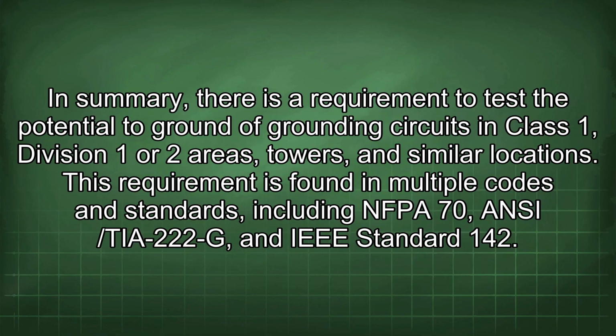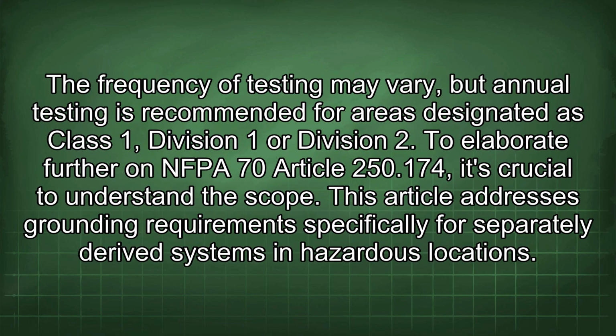In summary, there is a requirement to test the potential to ground of grounding circuits in Class 1, Division 1 or 2 areas, towers, and similar locations. This requirement is found in multiple codes and standards, including NFPA 70, ANSI/TIA 222G, and IEEE Standard 142.